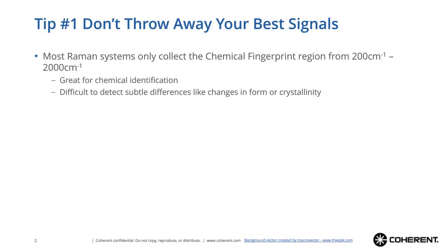My first tip is: don't throw away your best signals. It might seem kind of obvious, but actually most Raman systems only collect the chemical fingerprint region from 200 to about 2,000 wavenumbers. This is great for chemical identification, but it makes it difficult to detect subtle differences like changes in form or crystallinity for many materials.